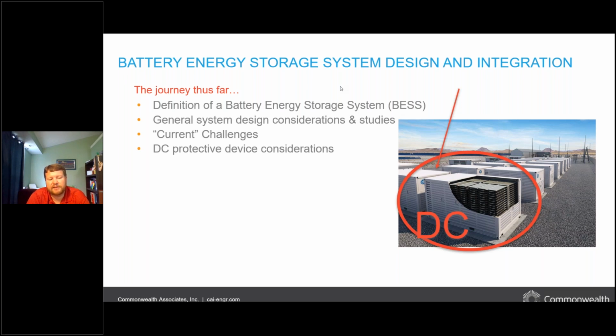If we talk about having a DC coupled battery system, you're going to have a DC to DC inverter in play here. And that DC to DC inverter is going to be able to see less losses because you're only going through one inverter to move power from a renewable DC source, for example, a type 4 solar or type 4 wind, to your battery system. I will state though, when we use DC coupling, although it's by evidence very much the most direct way to charge a battery directly off renewables, you do have the challenge that there's really not that many applications there, and you have a very limited supply of inverter manufacturers that will provide quality equipment to handle this.